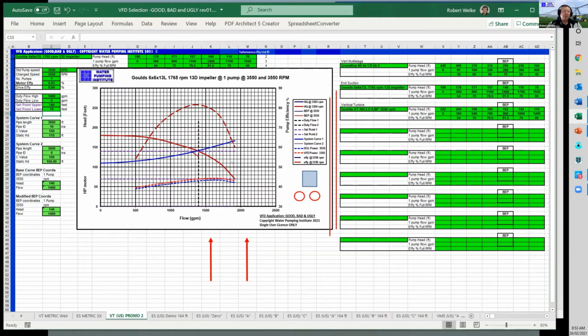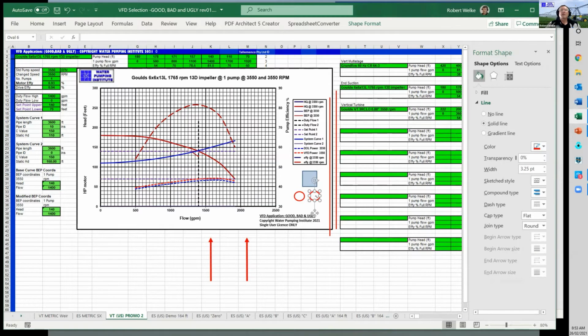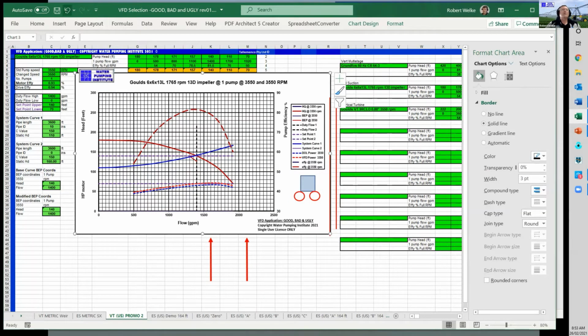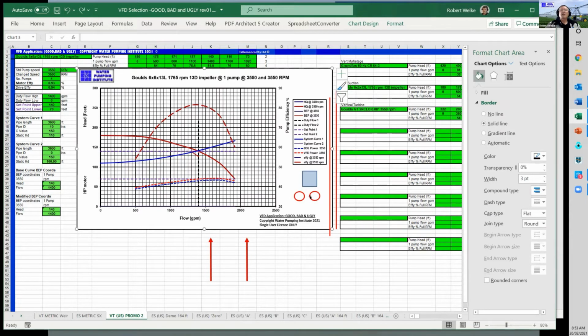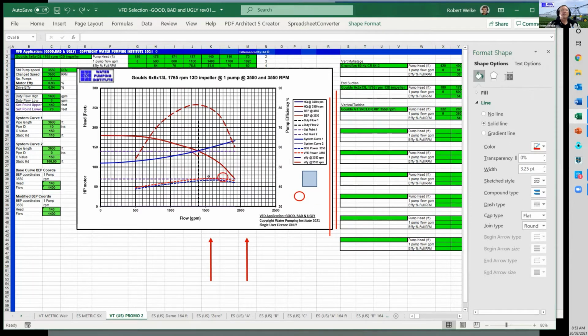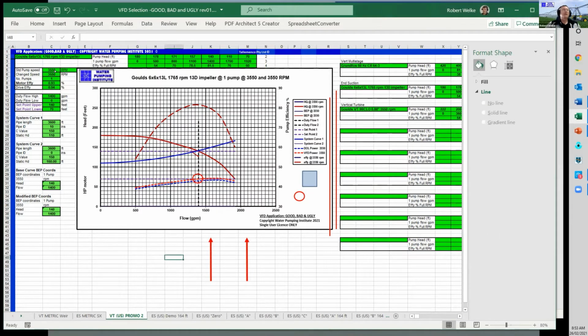Now we're going to lower the speed so that the pump curve intersects this point here. I've got a couple of indicators. Why is that not working? There. We want to lower the pump curve to that point. So we'll go up here and I'm going to hit 2875. I've done this before, so it saves time. If we slow that pump down to 2875 with a VFD, that pump output will satisfy our 1400 gallons a minute at 70 feet head. If we speed it up to full speed, it'll satisfy 1400 gallons a minute at 140 feet head. So there's the range.